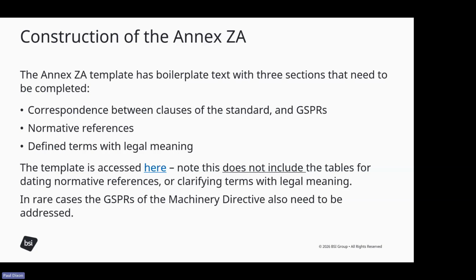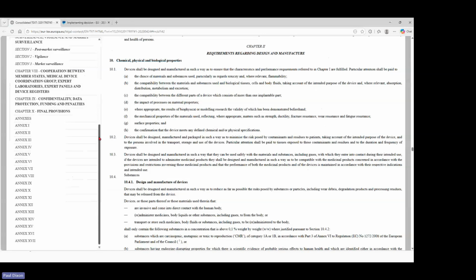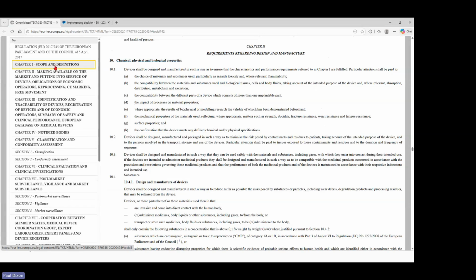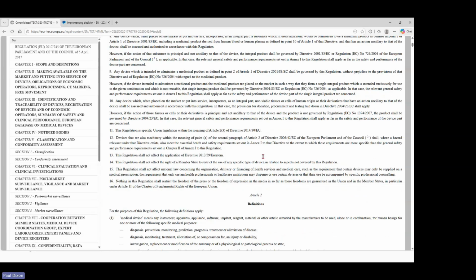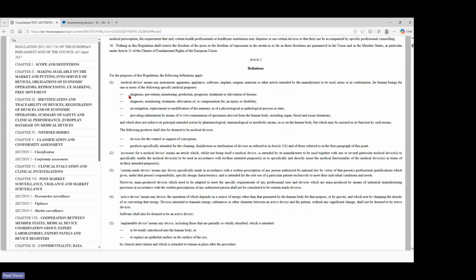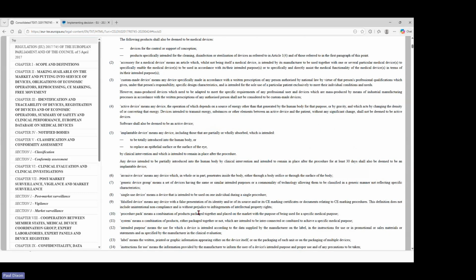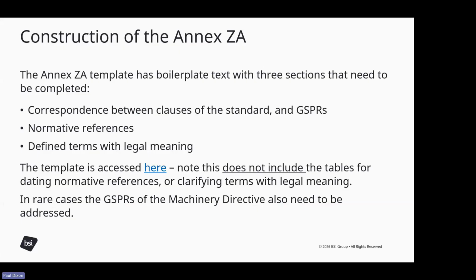So if I flip back to the medical device regulation, go back up to Article 2. Article 2 is a list of definitions. If your standard defines medical device or accessory or active device or anything else that's listed here, then you need to include the annex, the table ZA3 that addresses how that definition should be interpreted when referring to the standard. There's a link here for the template.